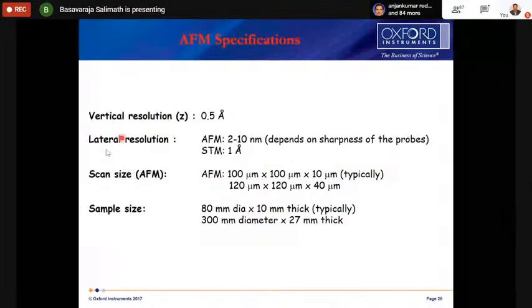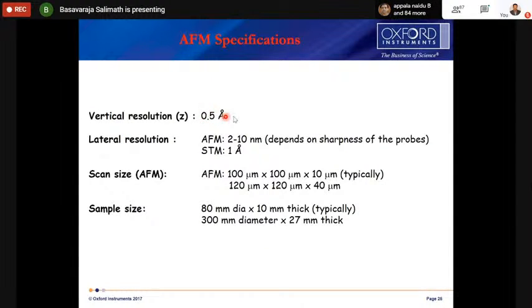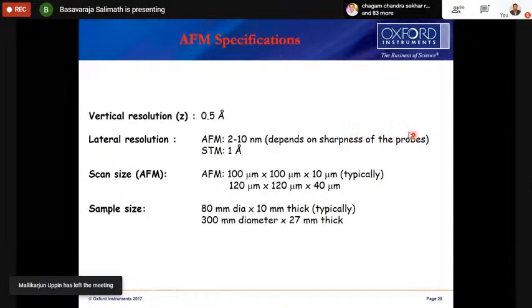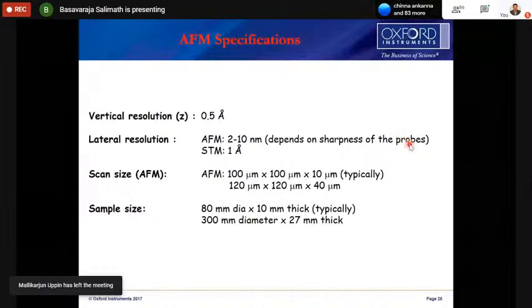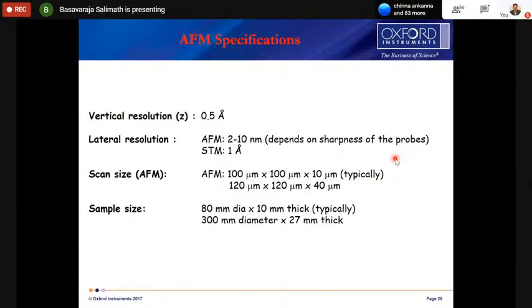So now coming to the AFM specifications, the vertical resolution can go up to 0.5 angstroms, and the lateral resolution depends on the sharpness of your probe. If your tip size is 2 nanometers, then we can get 2 nanometer resolution. In the case of STM, it's actually 1 angstrom lateral resolution.